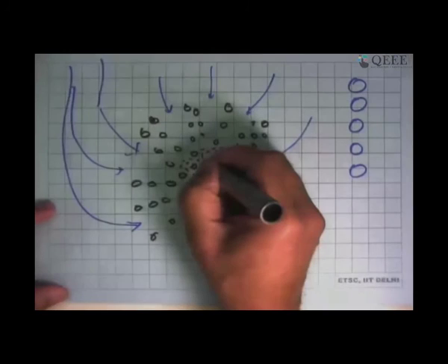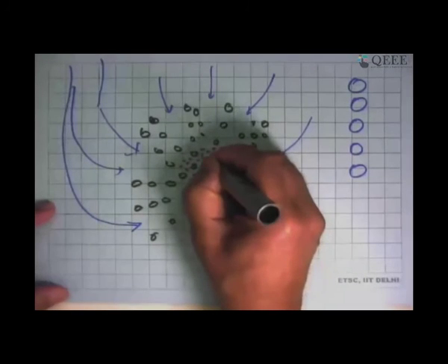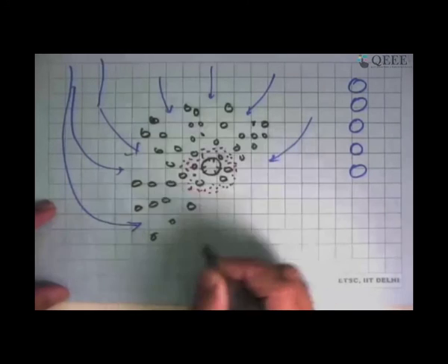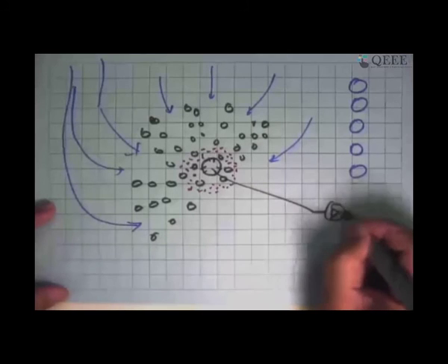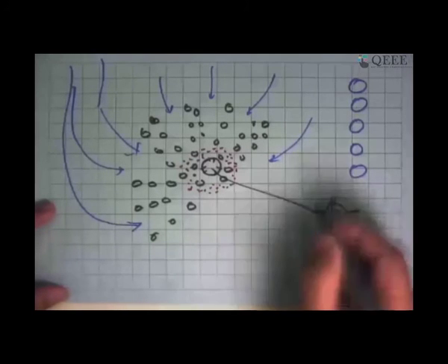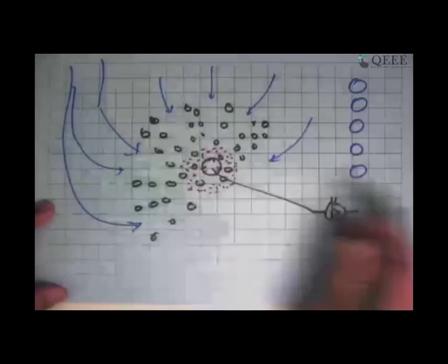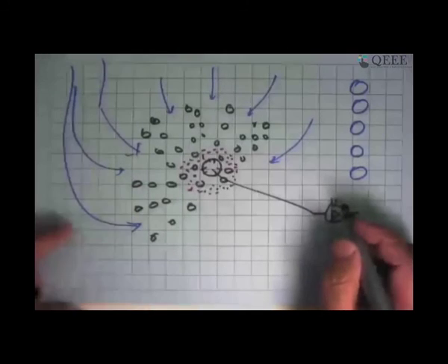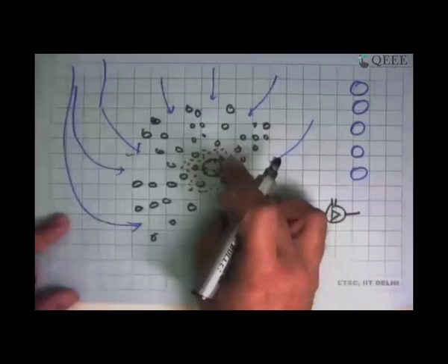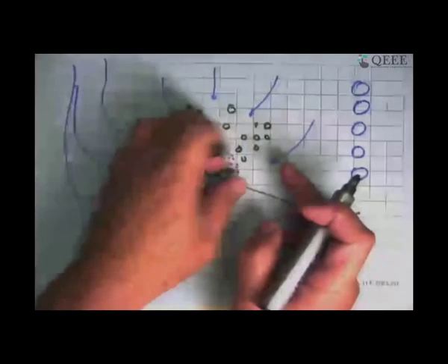And then what we did here, we put a big tube with openings in it, holes in it, and this tube is connected to a vacuum pump. So this is operating all the time and sucking out this thing. Some vapor will also go with it. But the important thing was that these N2 and O2 which came into the flow got accumulated here and got thrown out, and so that way we minimize the adverse impact of non-condensables.